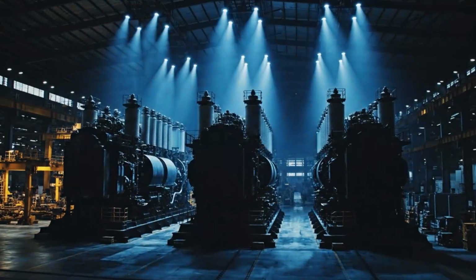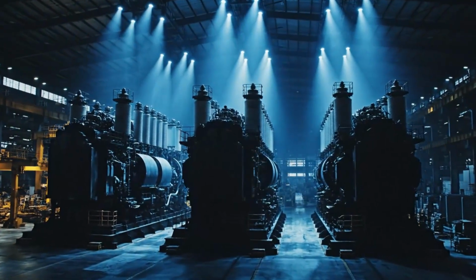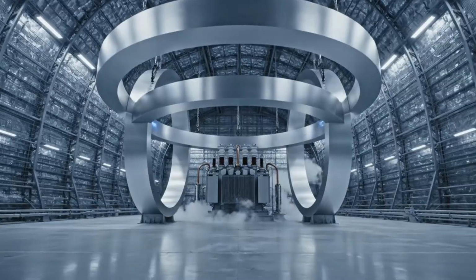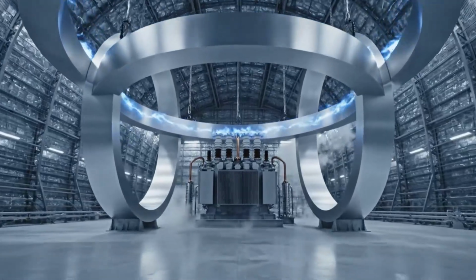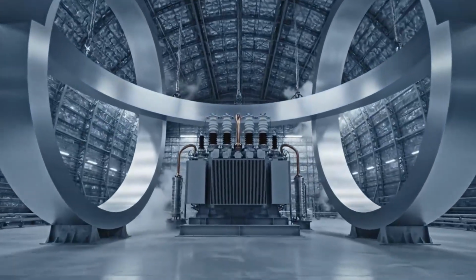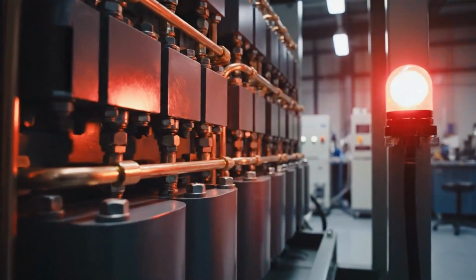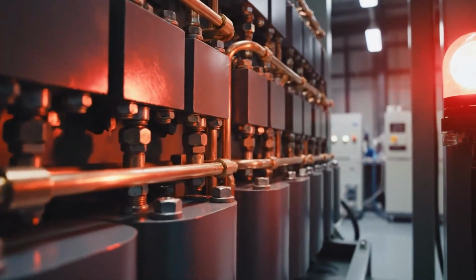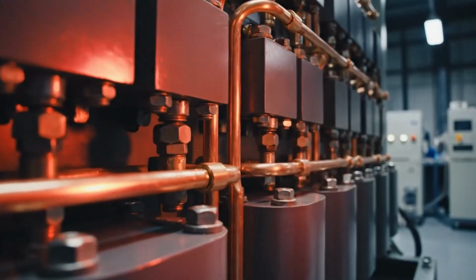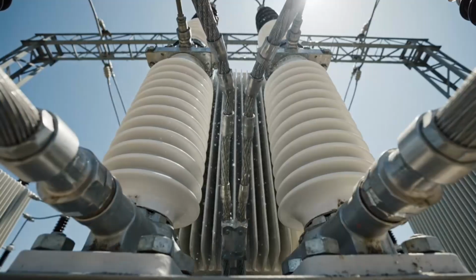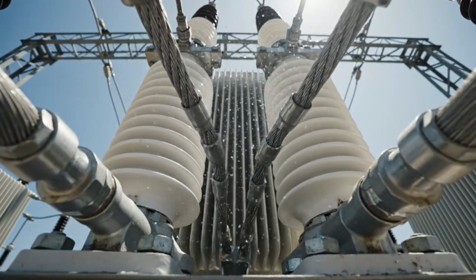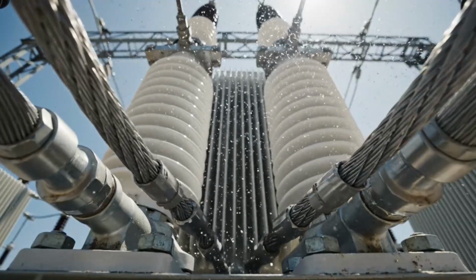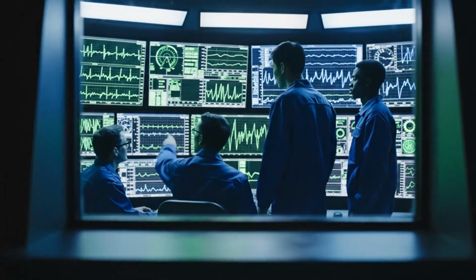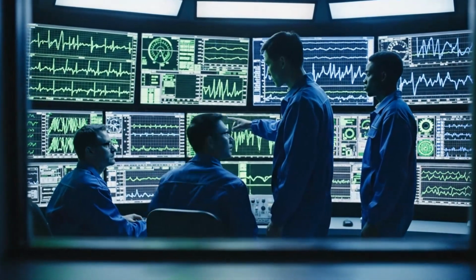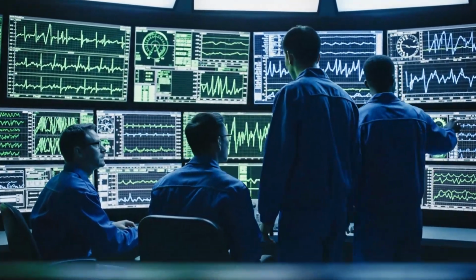Once the active part emerges from the vacuum chamber bone dry, the tanking operation begins. It is timed like a Formula One pit stop because every second of exposure to the humid factory air is a risk. The core and coils are lowered into the tank with only centimeters of clearance. Once inside, the heavy steel lid is secured with hydraulic torque wrenches. The transformer is now a hermetically sealed time capsule. Nothing goes in and nothing comes out.